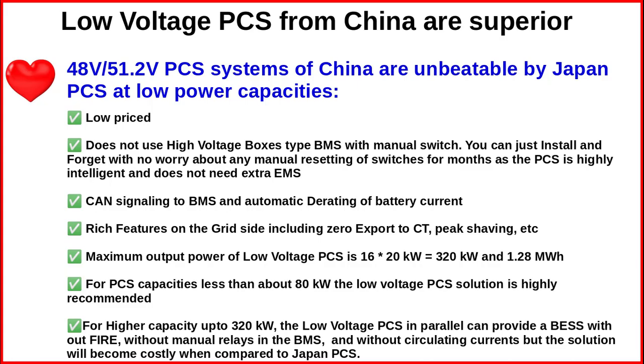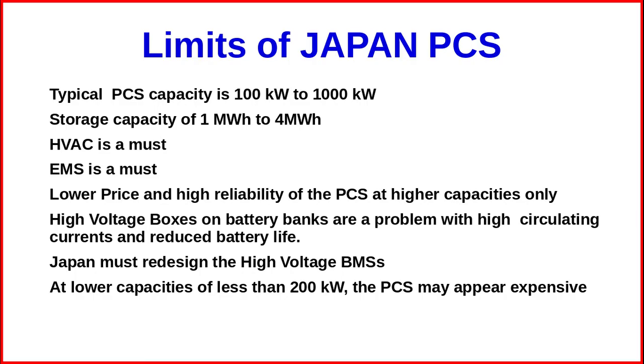So we have no risk of fire if we build a BESS by using the low voltage PCSs, which do not have manual relays in the BMS. We can avoid the fire in the BESS completely. So we have no circulating currents and no high voltage box relay. So we saw that the low voltage type China PCS is excellent. We also saw that high capacity Japan PCS is better than China PCS. Now let us see the limits of Japan PCS.